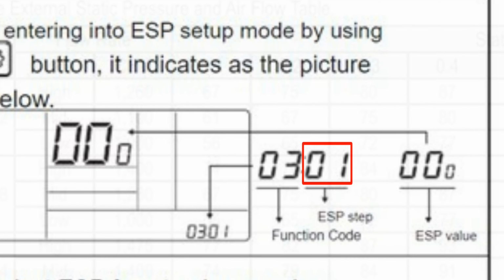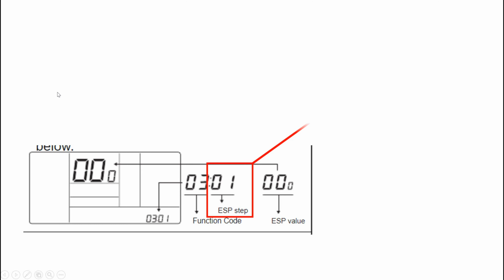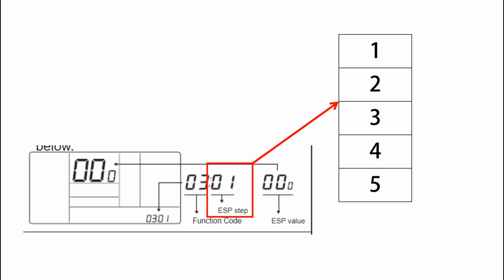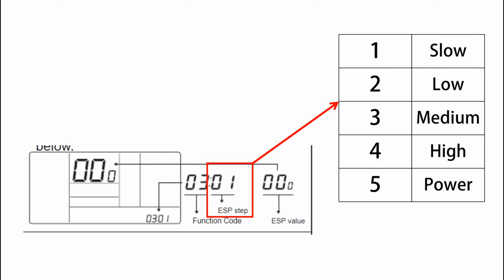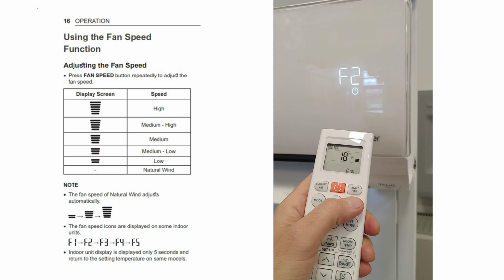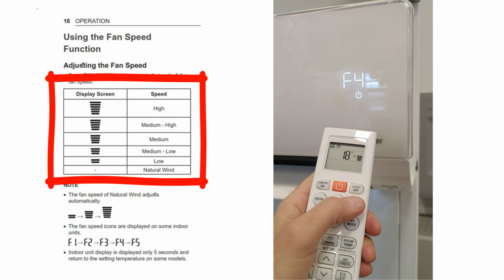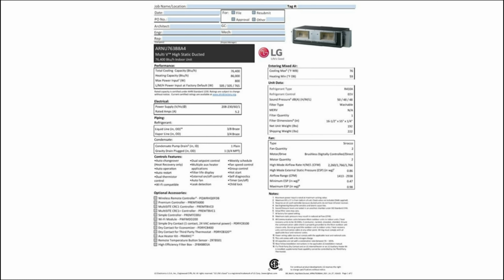Now let's talk about ESP step. ESP step has 5 levels, each level representing fan speed, which will be selected by user during the operation. Ductless units have 5 fan speeds, when ducted type indoor units have only 3 speeds, low, medium and high. And this causes a lot of confusion for technicians on site. Again, for ductless units we have 5 speeds of fan, when the ducted types of the indoor units have only 3 speeds, high, medium and low.